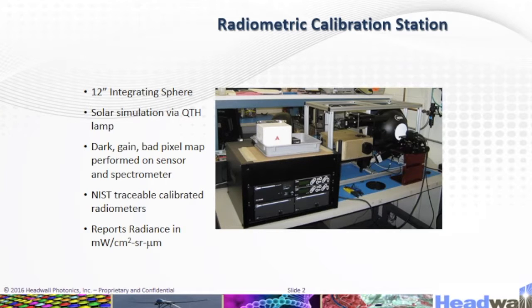Here we have a radiometric calibration station, shown in the picture. It's made of a 12-inch integrating sphere with a solar simulation and a QTH lamp. We have the dark gain bad pixel map performed on the sensor and spectrometer, and it uses NIST traceable calibrated radiometers.